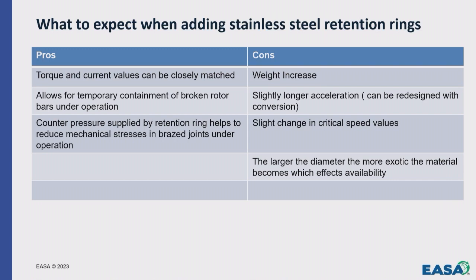A lot of times, we've all seen broken rotor bars. They tend to lift up through the iron. They can cause catastrophic damage. If you throw these stainless steel retention rings on, you can actually run them over the top of the bars. What that does is add an extra layer of safety: in the event of a rotor bar breaking, these rings will contain that bar for a longer period of time. Especially on 2 poles, we all know that everybody has every vibration whistle in the world on it. It might give your customer time to detect that something's gone wrong, and the motor can be pulled before that bar lifts up, takes out a winding, or severely damages the iron itself.